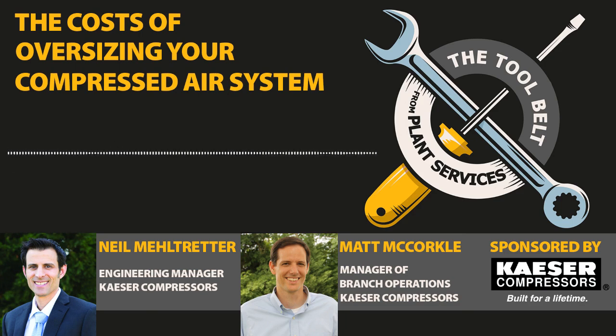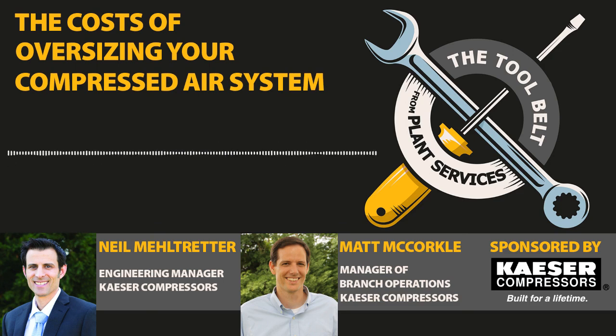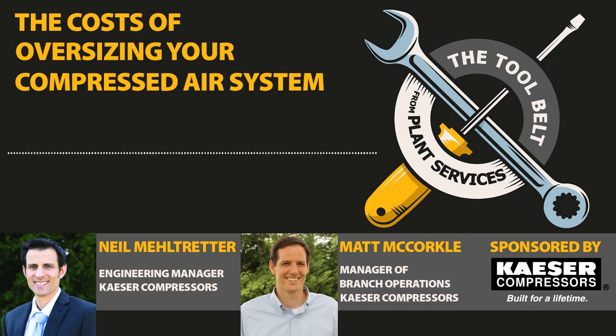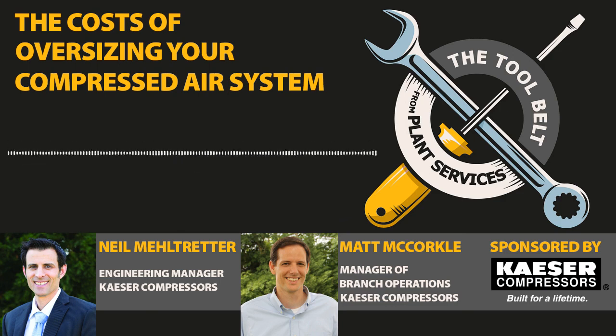The second one is storage. Storage is a great thing for any compressed air system. Going to the car analogy, you're looking at the suspension in that car, balancing out those demands. Neil talked about inconsistent pressure. Increased storage is going to help you stabilize pressure. Storage is generally always a good thing, and particularly good if you have really variable demands or very low demand for a period of time and your system is oversized. Also relatively low cost.